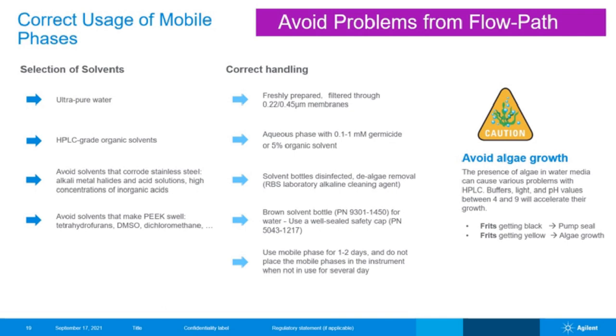The material in the flow paths are primarily stainless steel and PEEK. All solvents which can react with them should be avoided, or if not possible, a more regular maintenance of the concerned parts should be scheduled. The presence of algae in water media can cause various problems with HPLC.